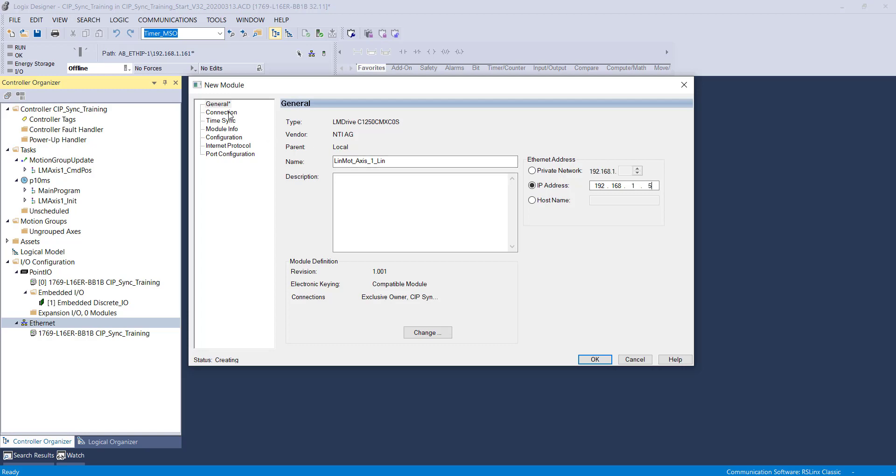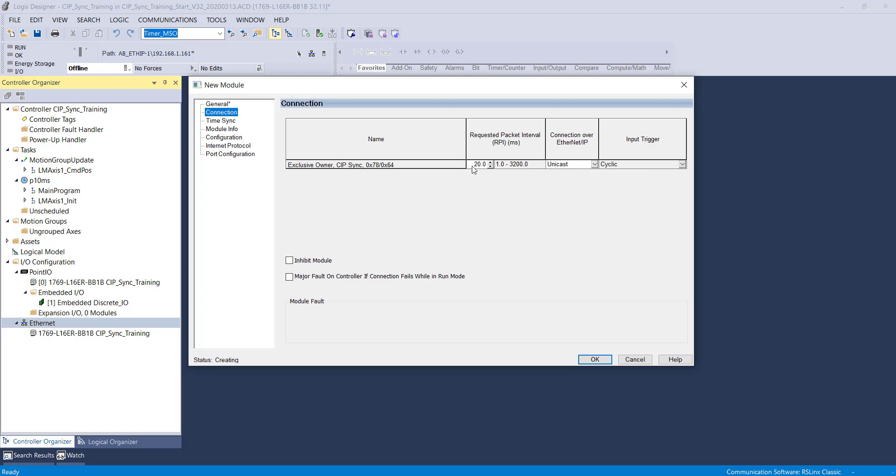Next, we will set the drive's RPI. The RPI of the drive should be the motion group update plus one.